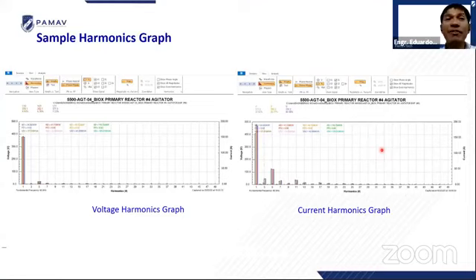Okay, we have a graph. Here we have a harmonic in a voltage graph. A VFD is known to have fifth and seventh dominant orders, so 5 and 7. And we can see it here visually in the current harmonics graph.